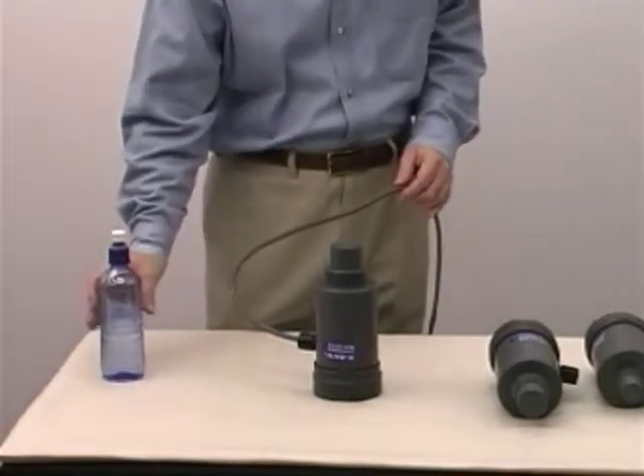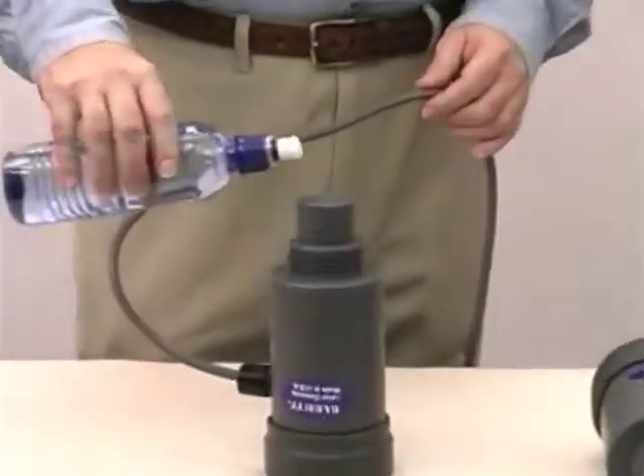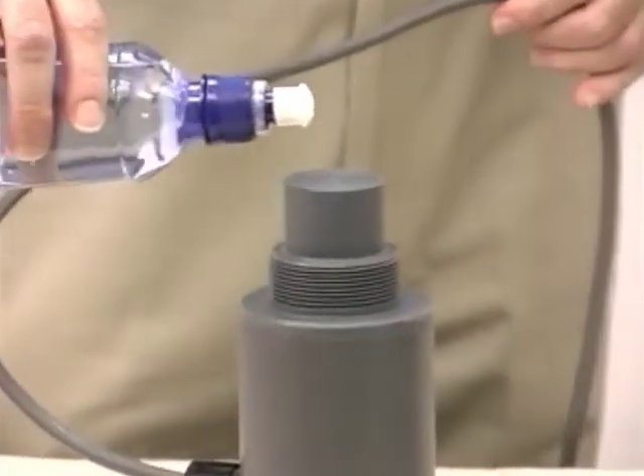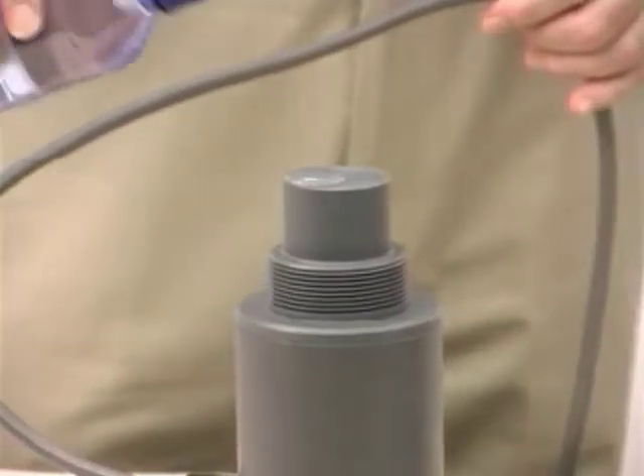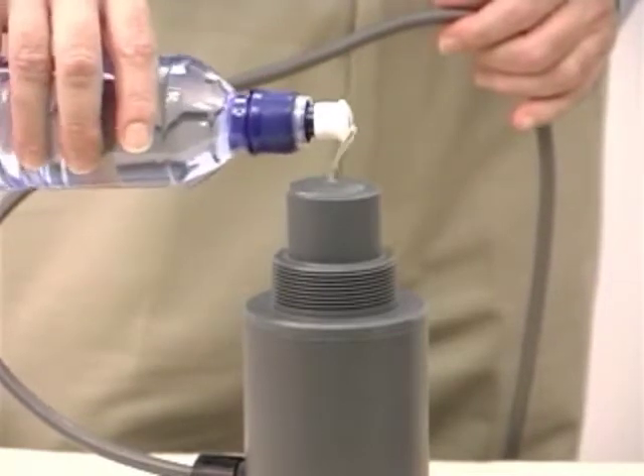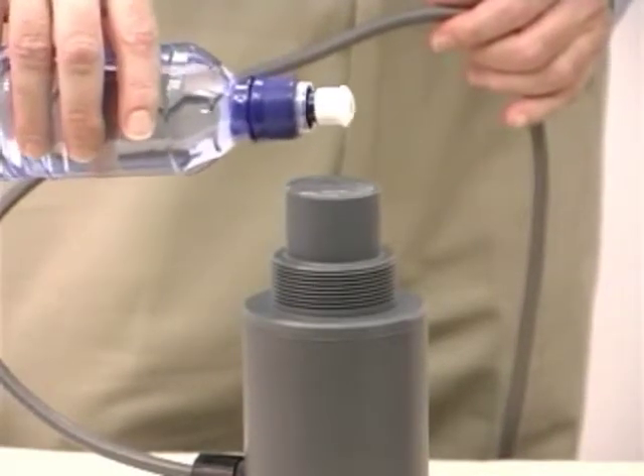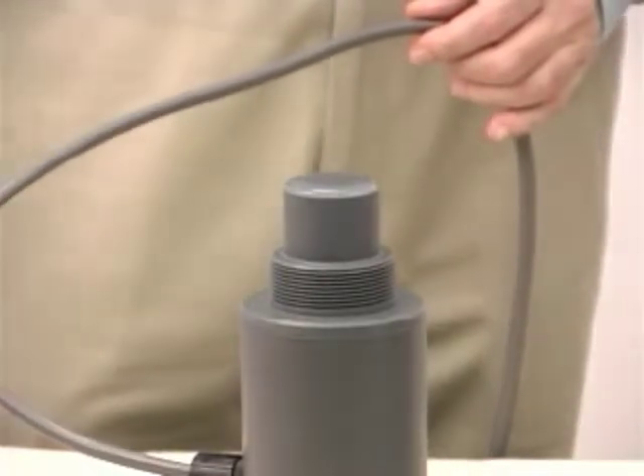This is also helpful if you have condensation on the face of the transducer. We've calibrated this unit so it's seeing the ceiling, and when I have water droplets on the face of the transducer, it still works just fine. In fact, it won't change the output a single bit with this much water trapped on the face of the transducer.